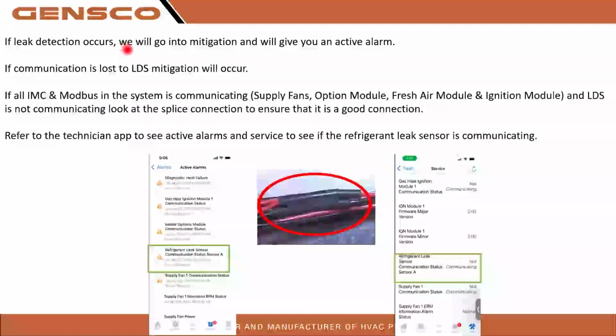If leak detection occurs, we will go into mitigation and we'll give you an active alarm. If the communication is lost to the LDS leak detection sensor, mitigation will occur. So if all IMC and Modbus devices in the system are communicating, supply fans, option module, fresh air, and if any of these do not communicate, it will activate an alarm in your app. We can go right into the alarm section right here, and we will be able to see that. This is why I love this system so much better than the Reliatel. Reliatel would just give us a two flash and we didn't know actually, we just knew there was a fault and you still had to dig into it to see what your fault was. This is actually going to give us communication status.